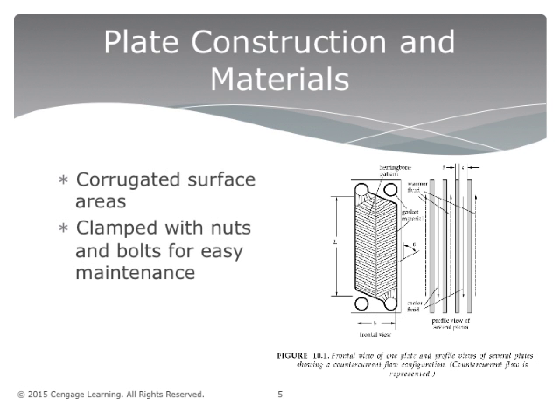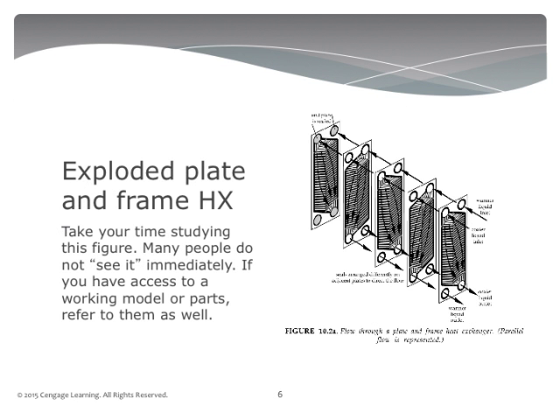The plates within the heat exchanger are corrugated. This imparts stiffness to the plates when they are clamped together. The corrugating of the plate surface also allows the fluid mixture to become turbulent, enhancing the transfer of heat. The construction of plate heat exchangers requires very little to no welding. They are often shaped through cold forming and clamped together with long bolts and nuts. This simple construction allows for easy disassembly and maintenance. The most common material used in its construction is stainless steel AISI 304.